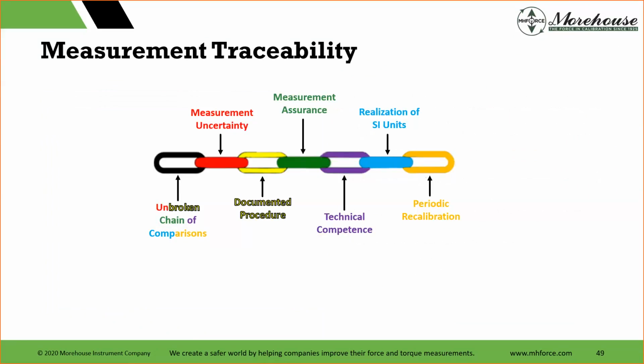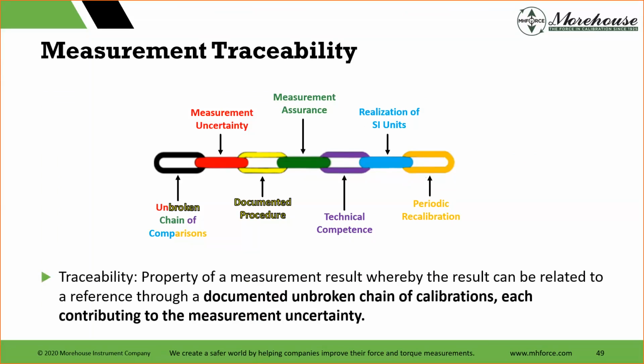We're looking at an unbroken chain of comparisons, and we're looking at measurement uncertainty, documented procedure, and the thing in the middle, that green, that measurement assurance holds everything into place. We're looking at technical competence, realization to SI units, and we're looking at periodic calibration. And this section goes pretty quick, but it's good to point this out. So traceability: property of a measurement result whereby the result can be related to a reference through a documented unbroken chain of calibrations, each contributing to the measurement uncertainty.